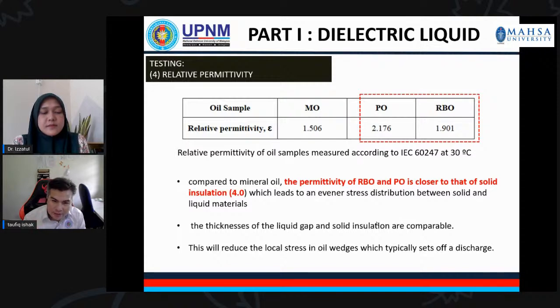Even though the vegetable oils have higher relative permittivity, what we suspect from this result is that the higher relative permittivity of vegetable oil is due to the structure, or we can say it's due to the presence of triglyceride molecules inside the vegetable oil, which differ from the molecules of mineral oil. So this triglyceride will contribute to the higher relative permittivity of the vegetable oil, which is polar in nature. Polar characteristic in nature for this particular transformer oil.